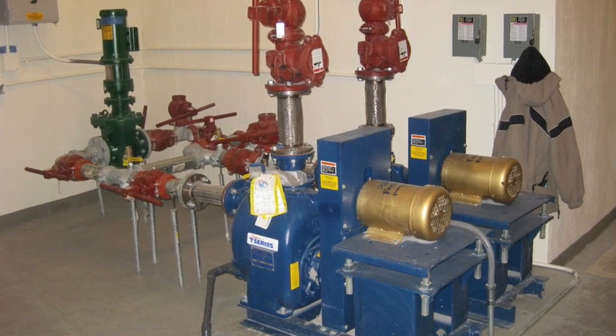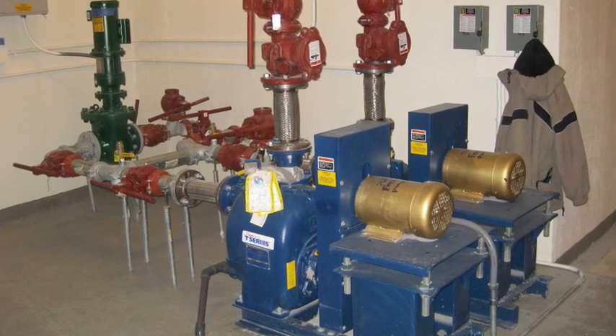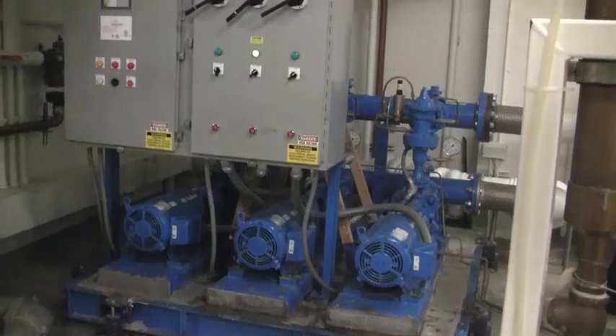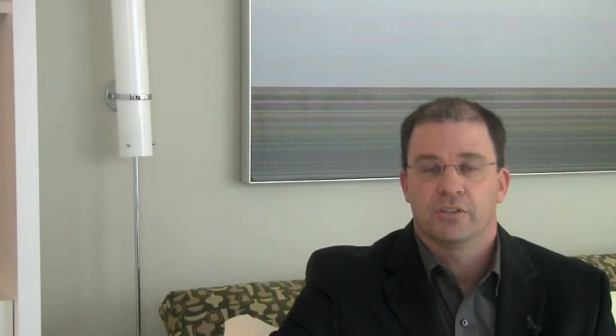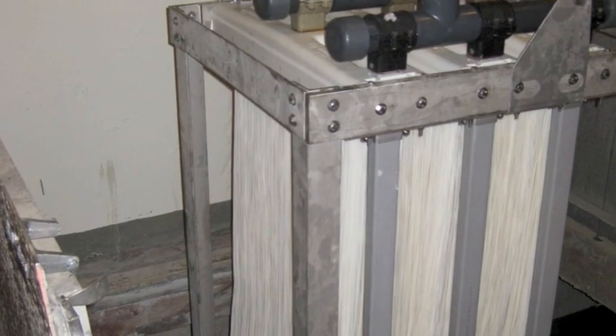The first process that the water goes through is a building sewer interceptor, and that interceptor runs through what's known as a feed tank. That feed tank essentially fluctuates and supplies the water to the system. From that feed tank, we have a series of pumps that pump through subsequent processes, which include nitrogen removal and BOD removal. Then the last and most important step is the membrane filtration process, where we actually have a physical membrane barrier that we pull clean water through and leave the solids behind.